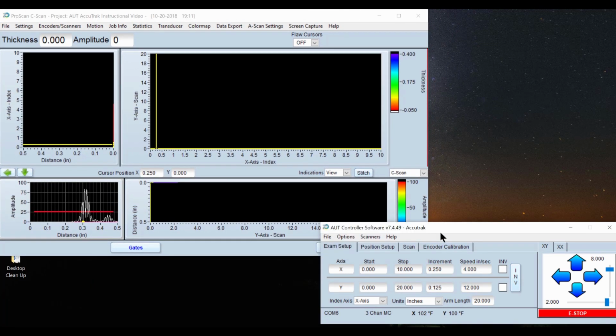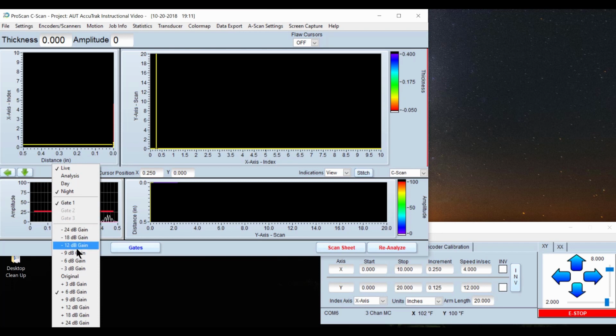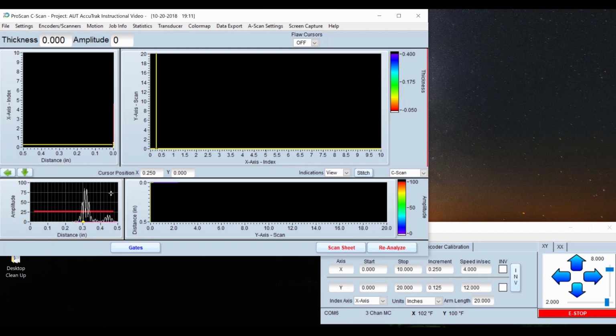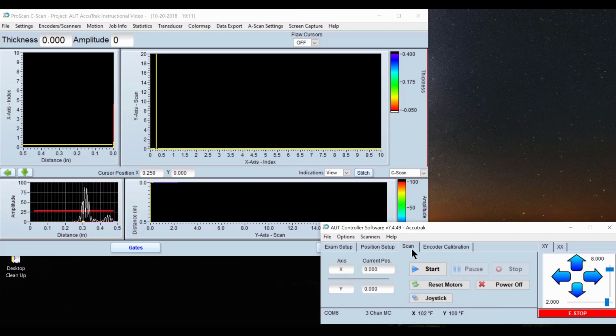So you will notice down here you have scan sheet reanalyze. These are features that will be available after the data. If you needed to add any soft gain in here or software gain, you could simply right click on the A scan and you can add or subtract gain here. If it's a huge difference, you might want to go back into your acquisition software A scan and decrease your gain. Alright, so now on to our test scan.